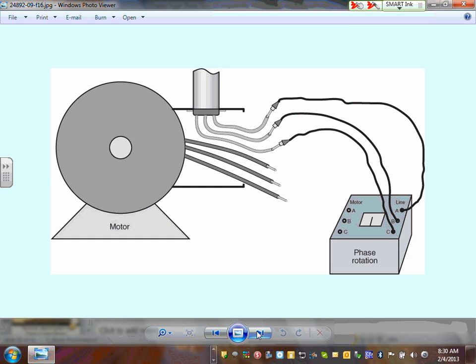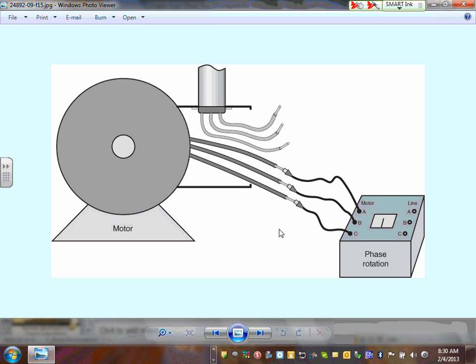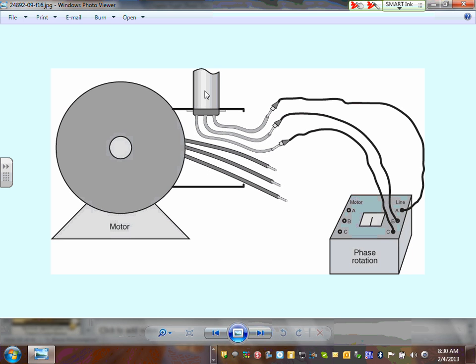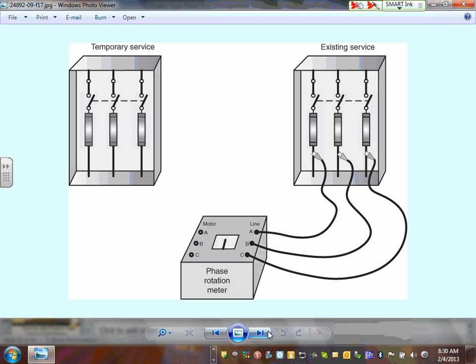Okay, so let's go here. We got that one. So here's how the rotation check works, guys. Here's my motor. Tie it to the motor. Make sure you spin the rotor. It gives you one indication, a correct indication. Go connect it to the line, and then when you connect it to the line, it should give you the same direction. If it's not, you just flip any two phases. Any two phases. You can also use it, Jeff, to test if you want to tie two systems together. You go to the existing building, and that will be your phase A, B, and C, and then you go to the new system. It should show A, B, and C correct. If it doesn't say correct, then all you have to do is flip two phases.